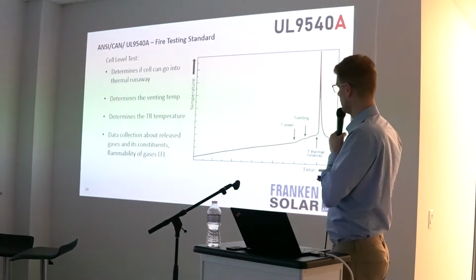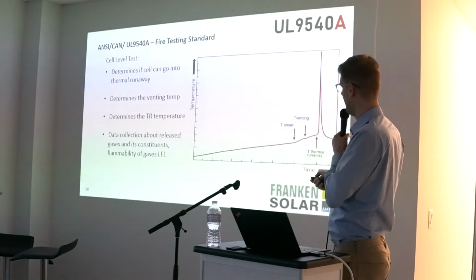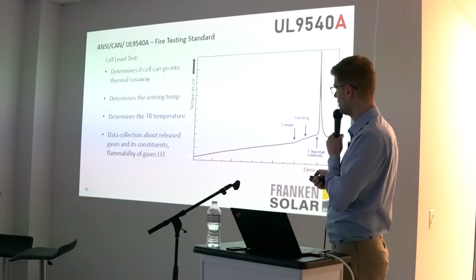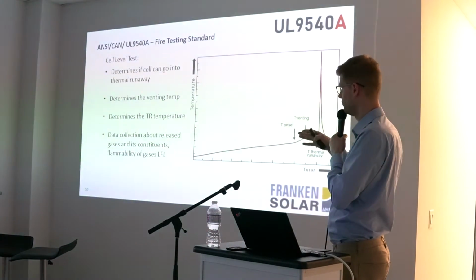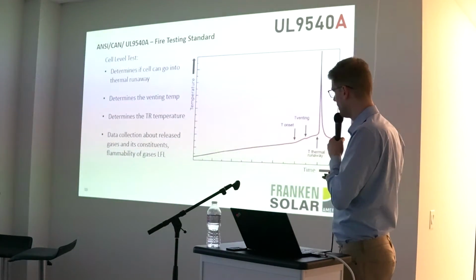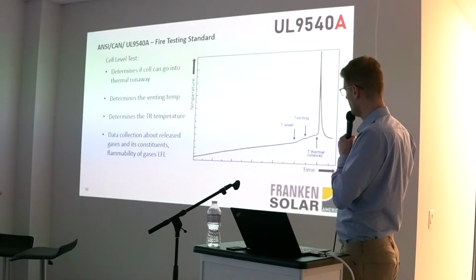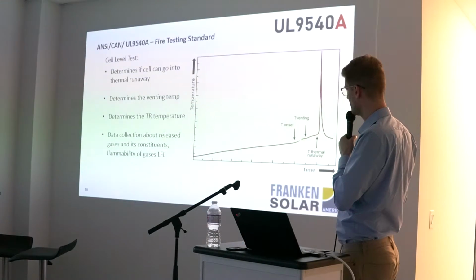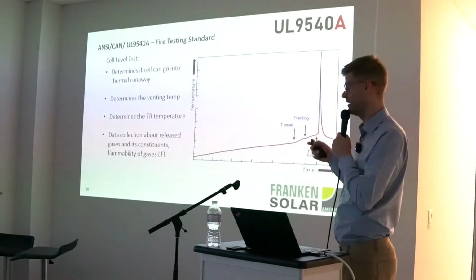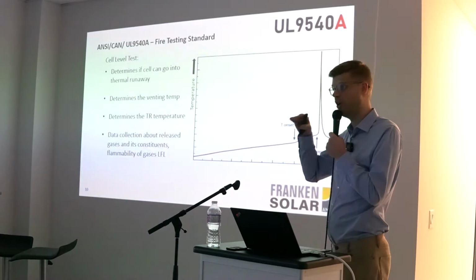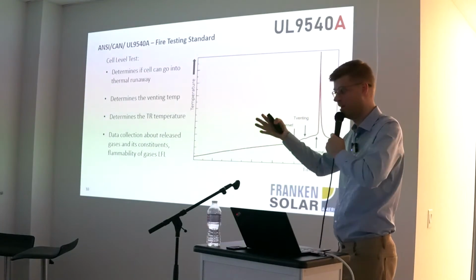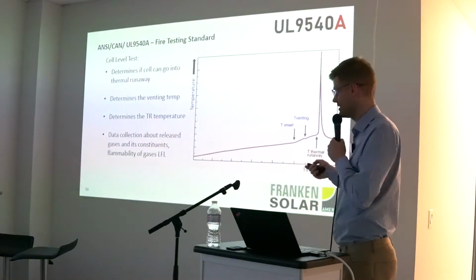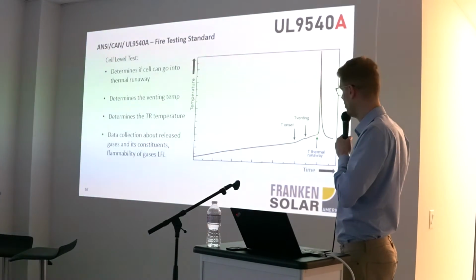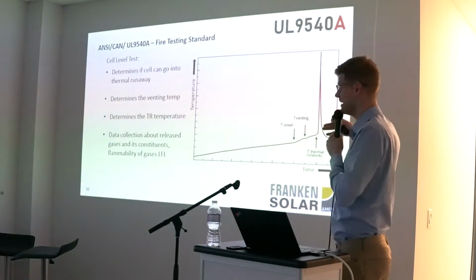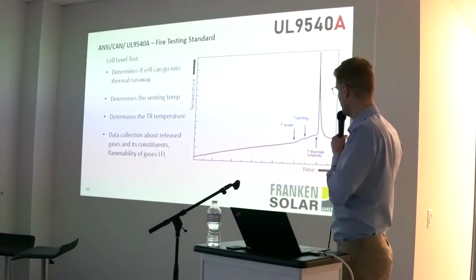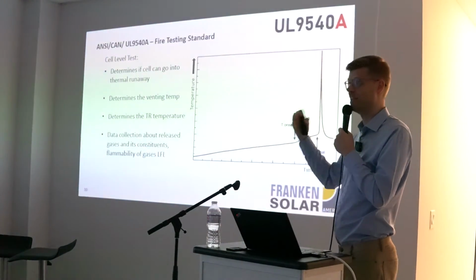of those released gases. So what we see here is a typical curve, temperature on the y-axis and time on the x-axis, and here the cell is being heated at about 4 to 7 degrees per minute. And it gets hotter and hotter. And at one point, there's a little rise in temperature, and here the cell starts venting, so the valve is opening. Once the valve is opening, the temperature stays a little more constant because you're releasing energy by venting into the environment. And at one point, the venting is done, and the temperature is still rising, until a point where the temperature is rising uncontrollably, and that's your thermal runaway event. And that's pretty much the critical moment where the system is not in a stable situation anymore.